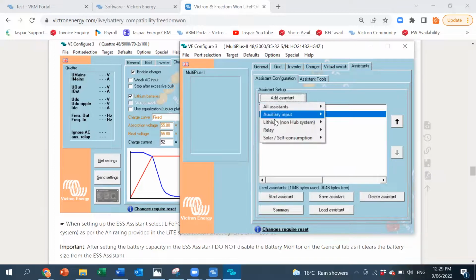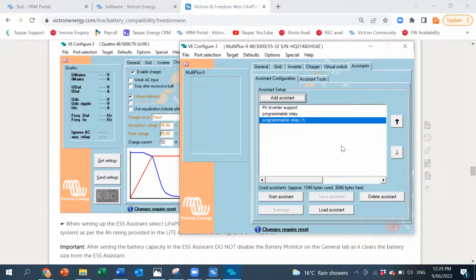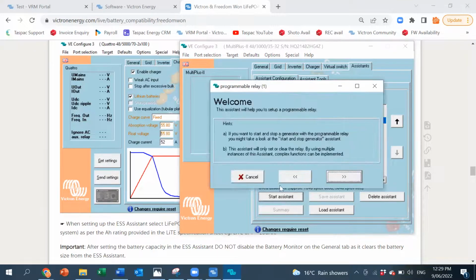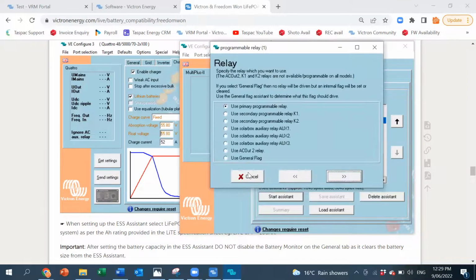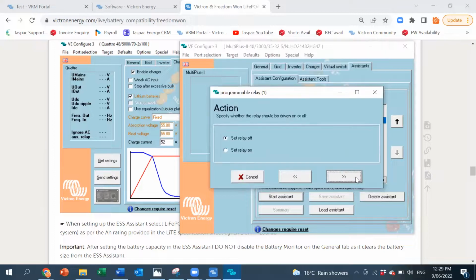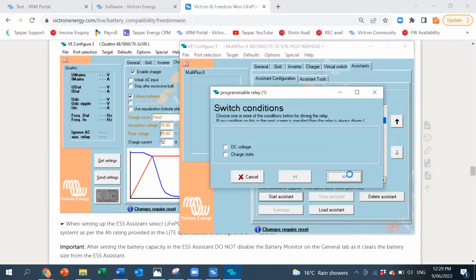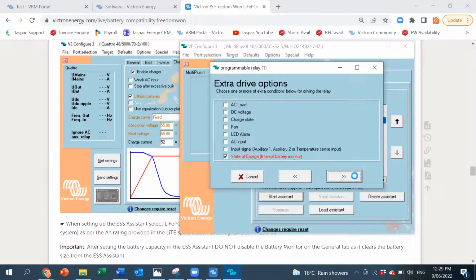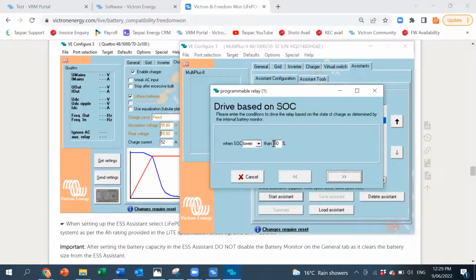And then I'm going to add another assistant in there, relay assistant again. And this time I'm going to do exactly the same thing, except I'm going to tell it to turn off, set the relay off, when the state of charge is below 96%. You can arbitrarily set whatever you think, whatever you see fit for those settings. Generally you want to keep them pretty high because you don't want the hot water cylinder sucking the battery dry at the end of the day, because you want them to last through the night.